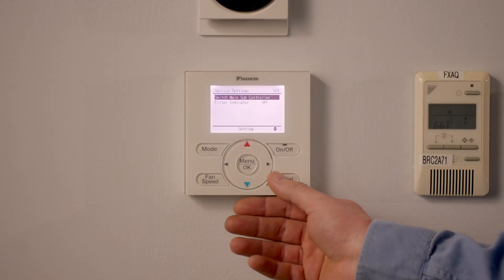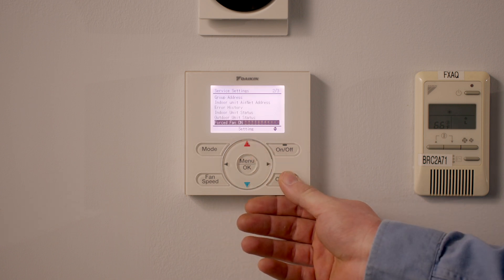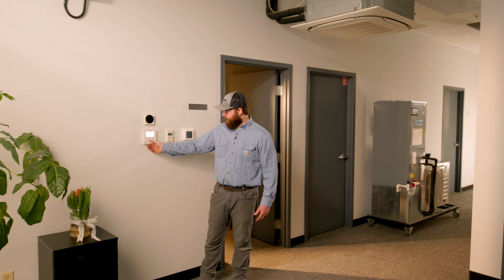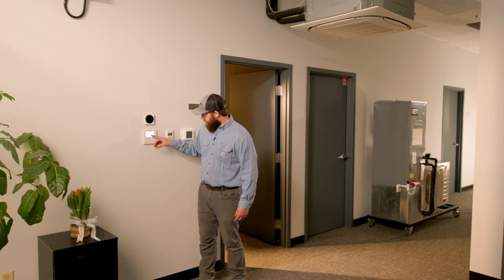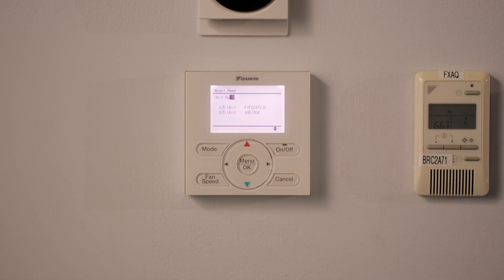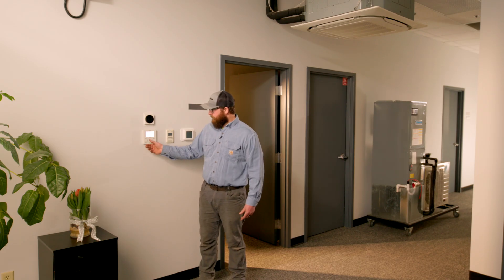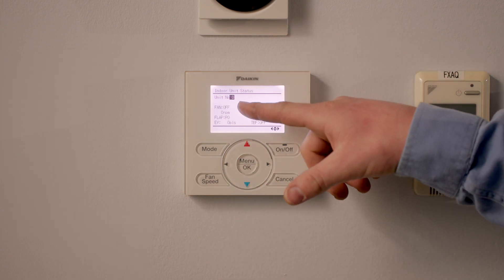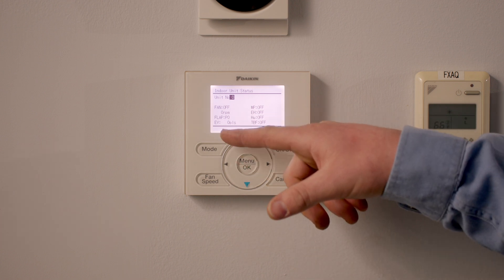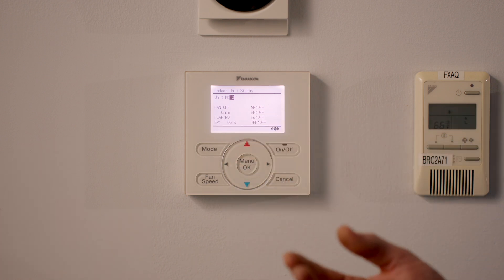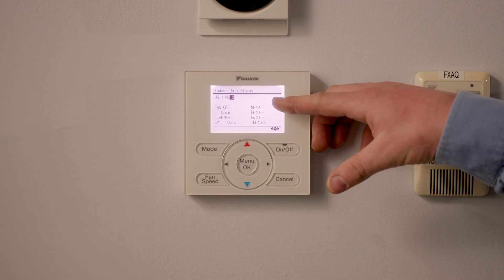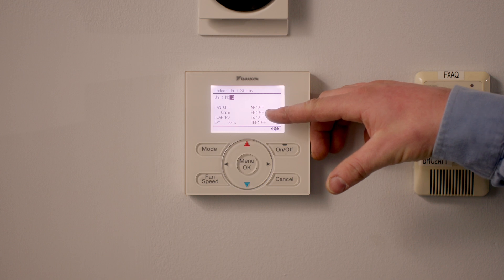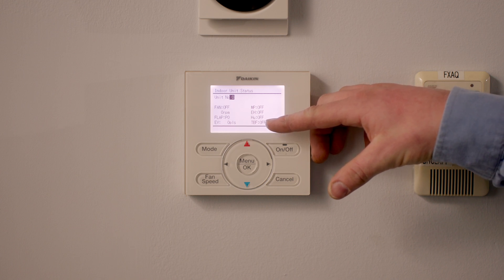We can also see if we go into the maintenance menus — we hold down the cancel button again within the service settings. Now we're in the maintenance menu where we can see the model name of the specific indoor unit. In this case, we have an FXFQ24TVJU. We can see another indoor unit status menu here, which will populate whether our fan is on or off, what speed it's running, what position the flaps are in, what position the EEV is in, whether our condensate pump is running, if we have an electric heater and whether it's on or off, humidifier on or off, or TBF on or off.